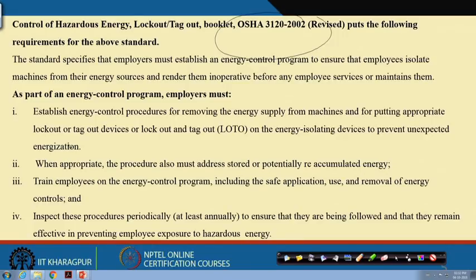And put appropriate lockout, tagout devices — or lockout and tagout both, which is called LOTO — on the energy isolating devices. They say: isolate the energy, then put the lock, tag, or both. When appropriate, the procedure must also address stored or potentially re-accumulated energy.